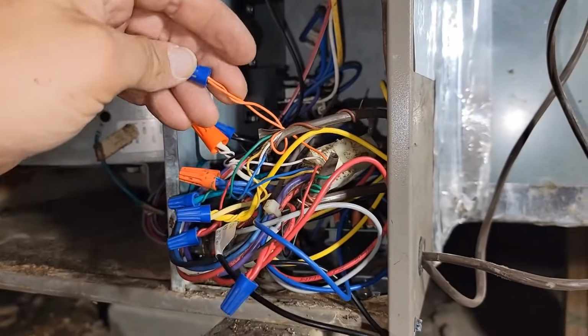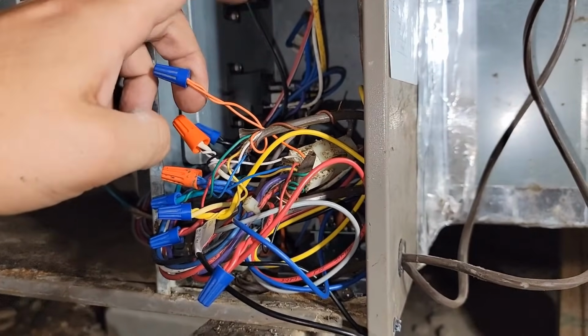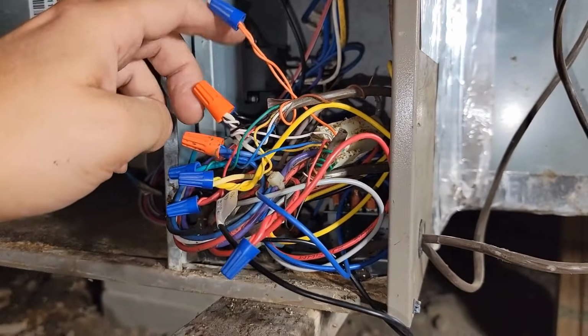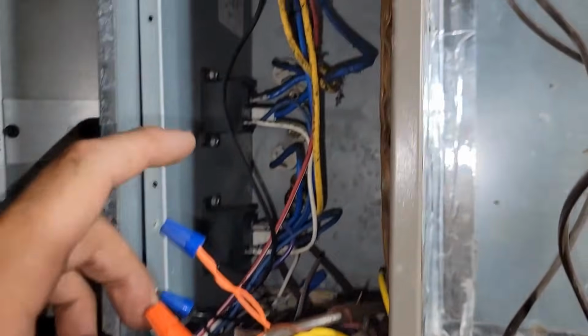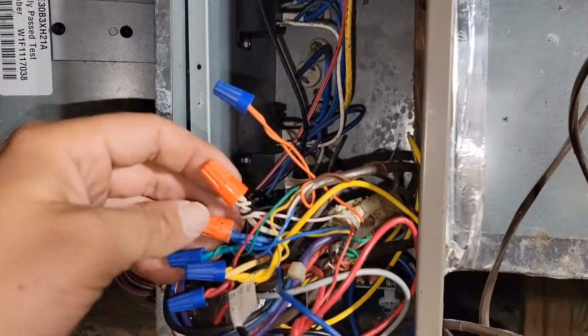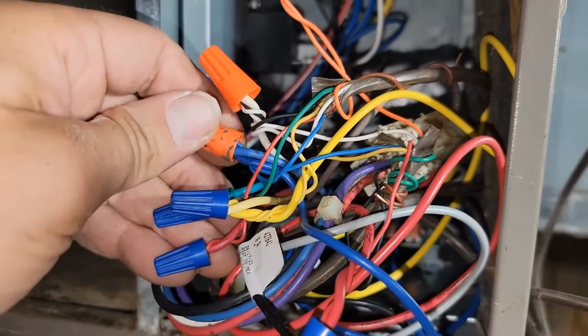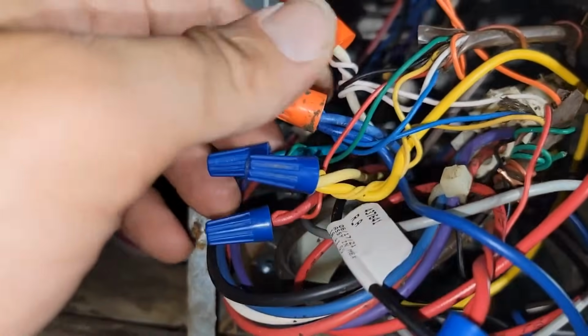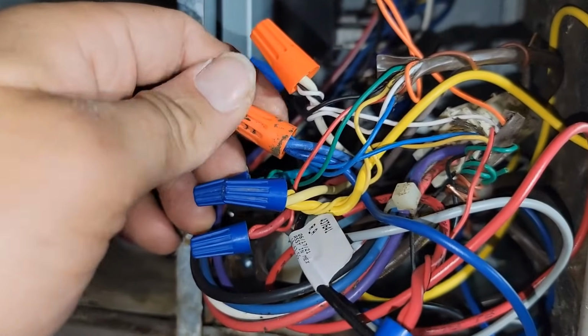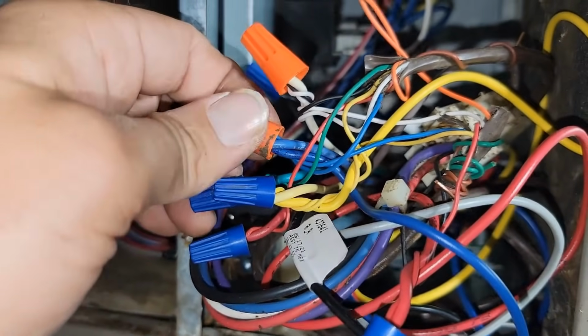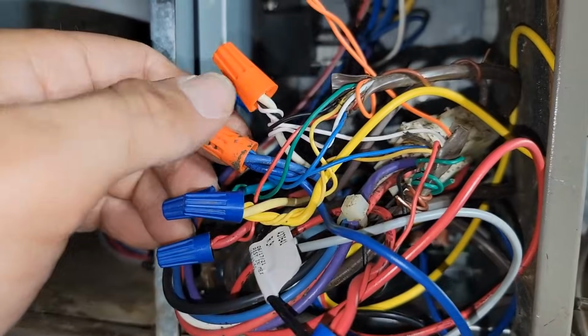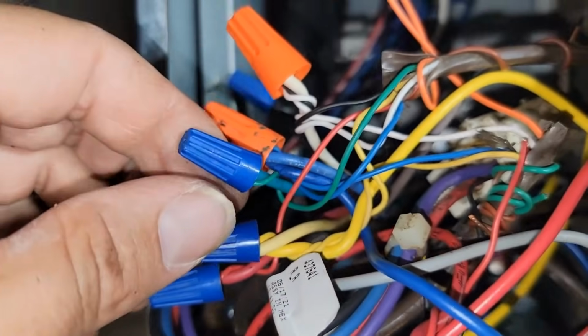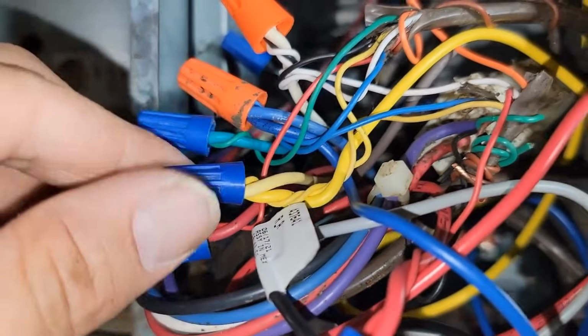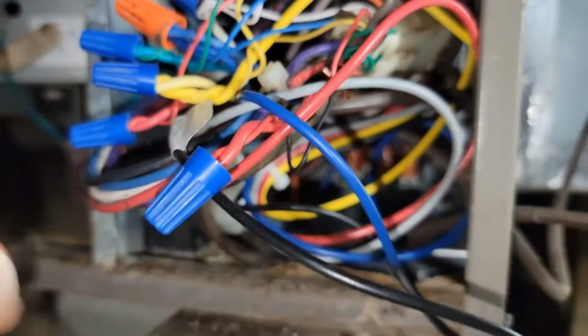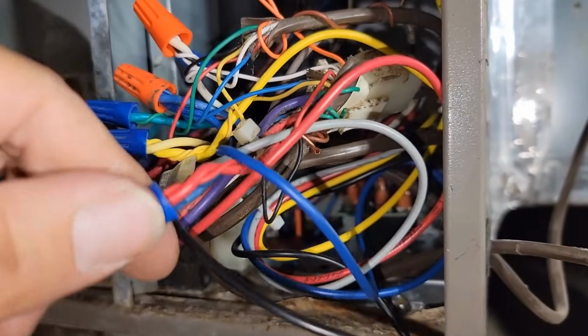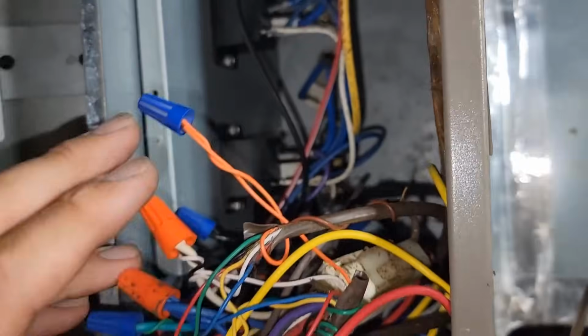This is our reversing valve wire. It goes from the O terminal of the thermostat to the outdoor unit. This is our W1 and W2 because we're not gonna stage the heater kit. This is a 10 kW. It needs to come on all at once and doesn't need to be staged. This right here is our C wire from our thermostat to our common of our transformer and our air handler, and then to our outdoor unit C. This is our G wire, energizes fan only, Y1, R1, and this goes from our relay to our S1 of our outdoor unit. And that's the wiring.